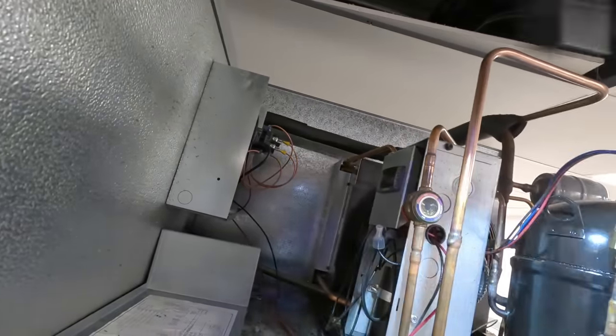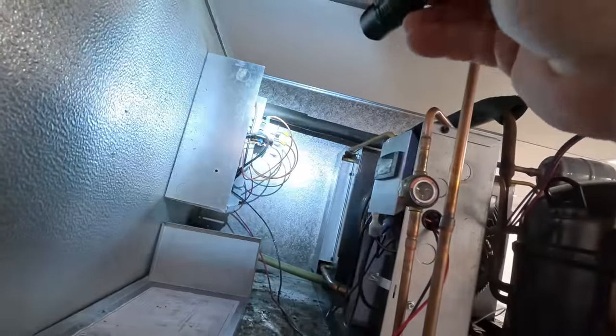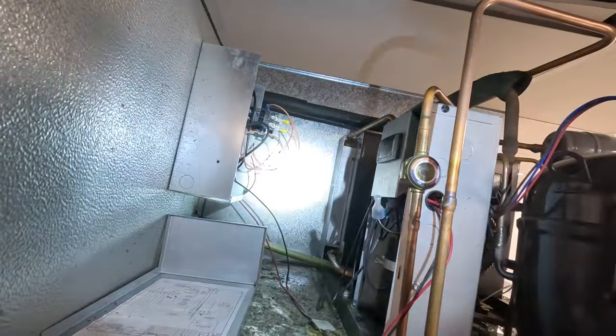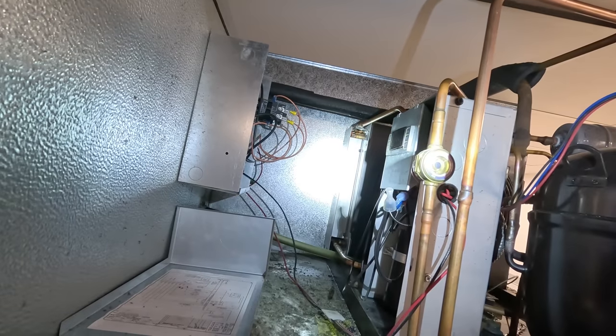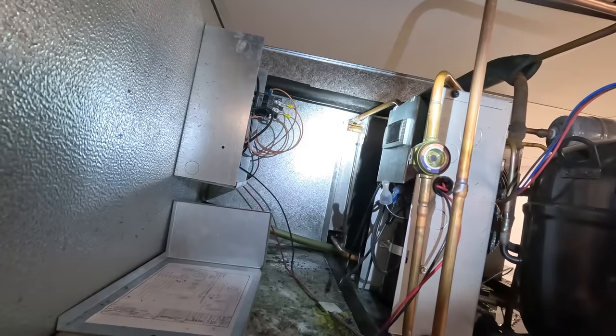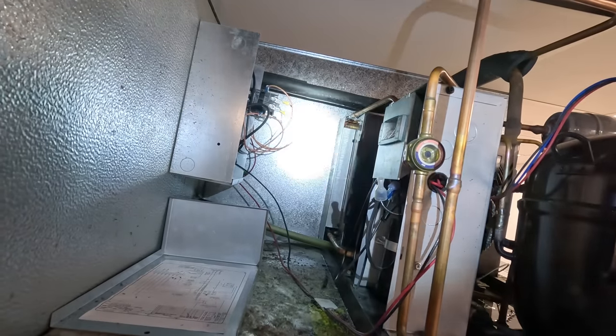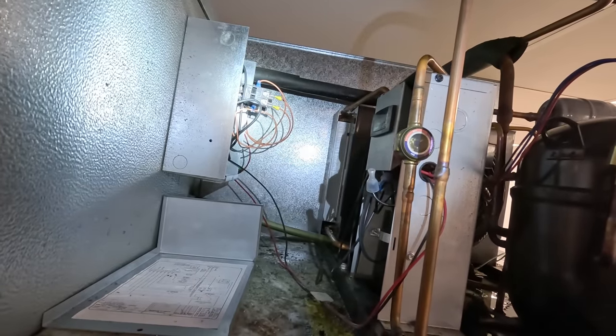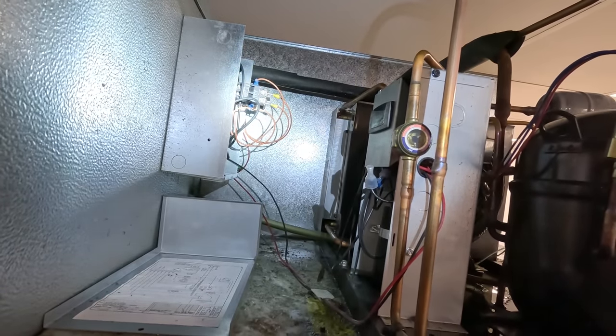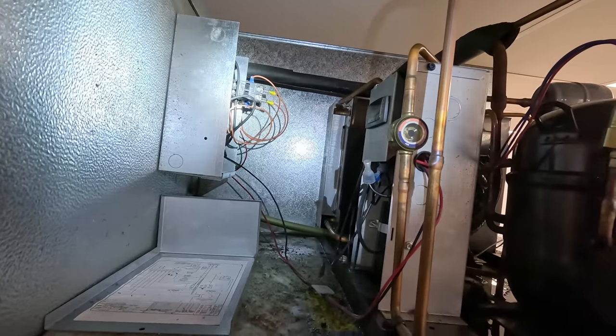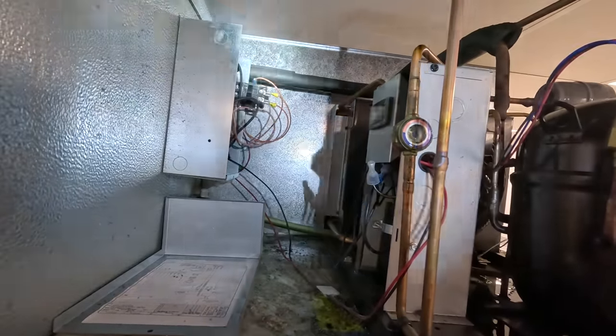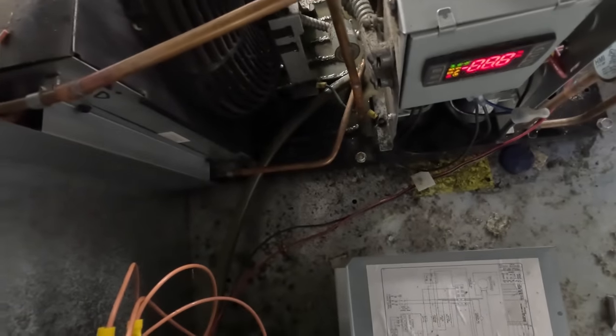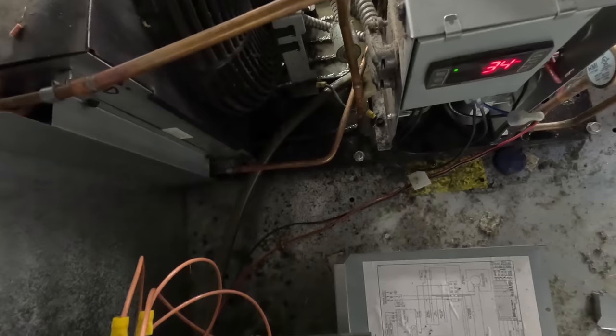Contactor pulls in, which means this should be getting power, but it's not. I don't know what the story is on that. I don't know if I should just wire it hot and all the time or not. I mean, when I turn the power off and back on again, it came right on. So I don't know if there's a delay in the compressor, but not in the evaporator. That seems pretty fishy. There should be a delay even in the fan, but obviously it's not coming on right. I did match them up left and right to the right one, as far as I know. Yep, there it goes. Alright, good. There must be a delay there.